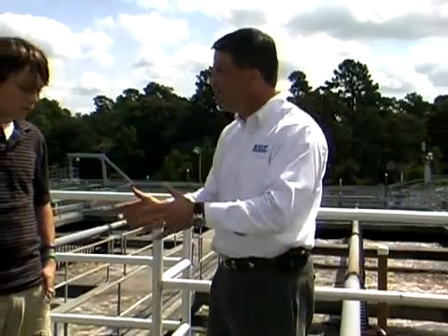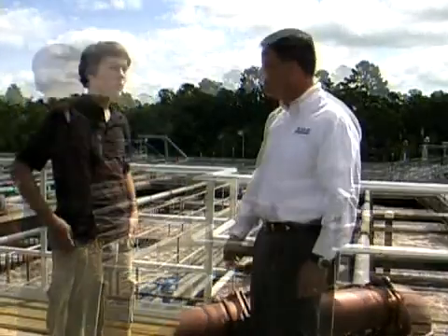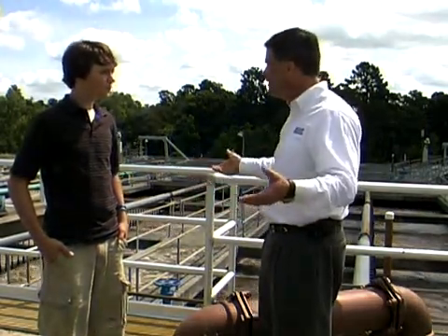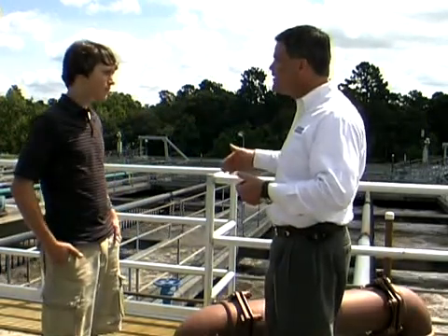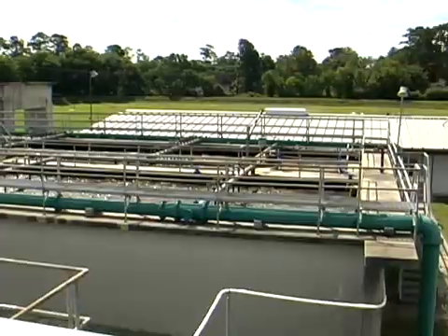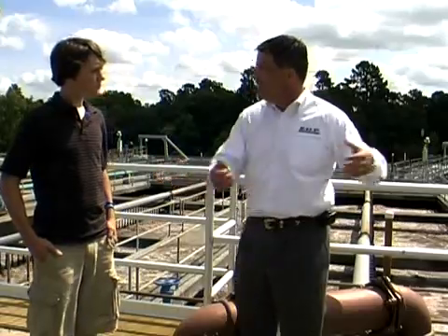So we just convert all the organics to bacteria, then we remove the bacteria by gravity, leaving behind the treated water. So where does all that bacteria actually go after you're done? Okay, so we're growing bacteria all the time. We grow probably 35,000, 40,000 pounds of bacteria every day at this plant. Well, some of it comes back into the process and does the job again. We recirculate it. But the amount that we grow every day, we try to take that out and put it into a separate process. Over here is a separate process called the digester. We put all that extra bacteria into the digester.